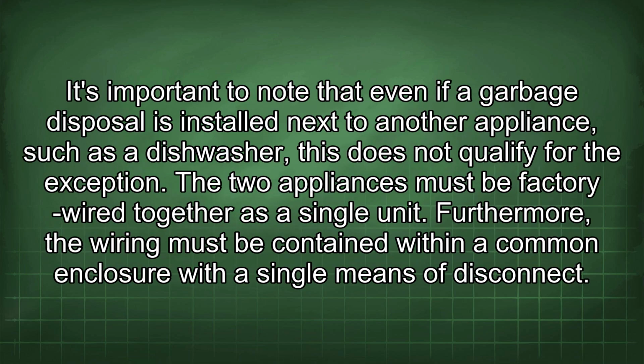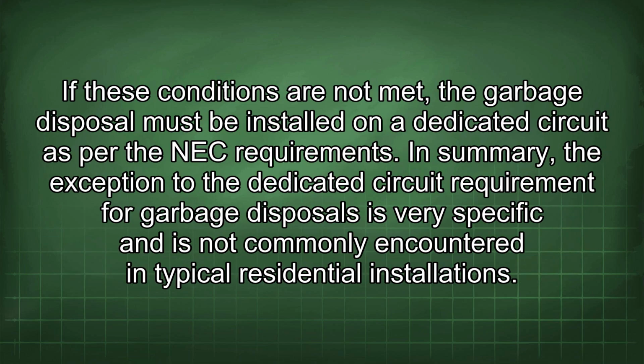It's important to note that even if a garbage disposal is installed next to another appliance, such as a dishwasher, this does not qualify for the exception. The two appliances must be factory wired together as a single unit. Furthermore, the wiring must be contained within a common enclosure with a single means of disconnect. If these conditions are not met, the garbage disposal must be installed on a dedicated circuit as per the NEC requirements.